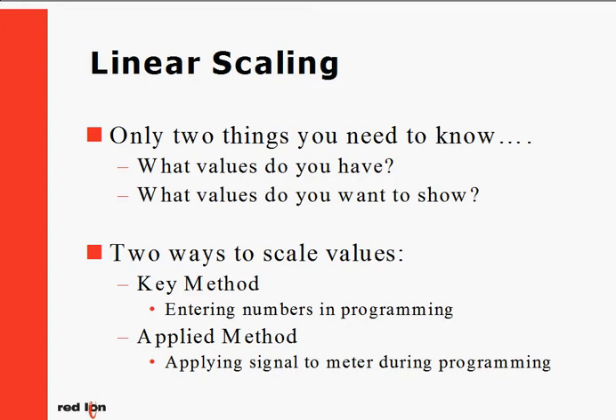One way is the Keyin method. This method should only be used if the operator knows his exact input values and display readings. The most common way is by using the Applied method. This method is used by actually applying the input signal to the meter for scaling, rather than programming in any values.